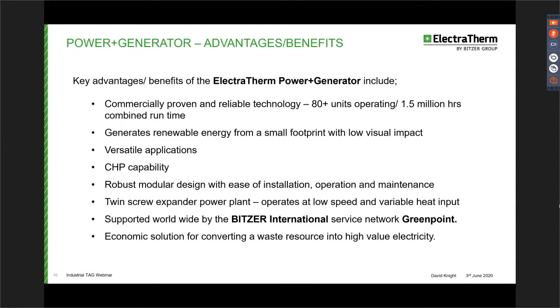So a client comes to us with a potential project. We do an evaluation, and our first evaluation is we look at how we're going to cool, whether it's a radiator or whether there's alternative water. We then select the type of expander, type of machine, and whether it's a 50 hertz or a 60 hertz application. We enter the heat input, and at this stage it's 150 degrees centigrade, 11.9 liters per second. We look at the cooling water. If we're using a radiator, we enter the ambient temperature. If it's an alternate cold water service, we put in the actual temperature of the cold water. And by pressing the click here to calculate button, we get our results. In this instance, it's 125 gross power with 104.7 net.